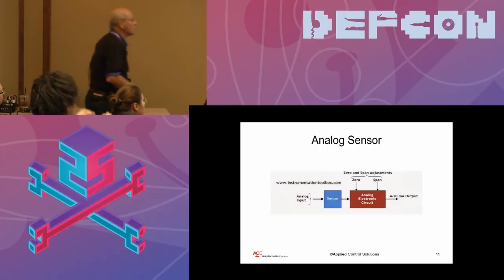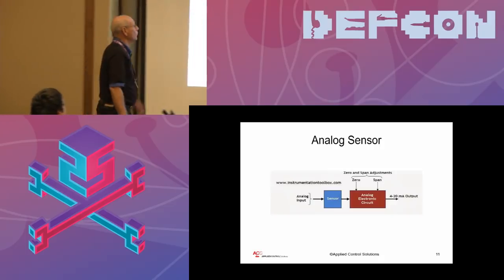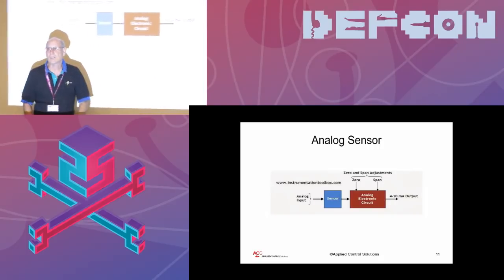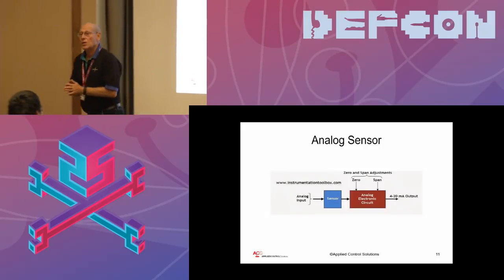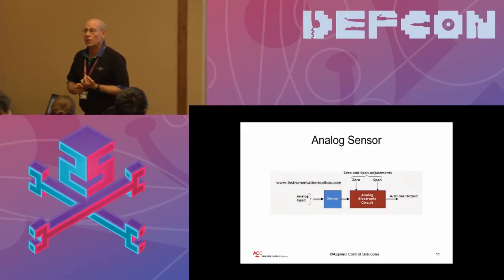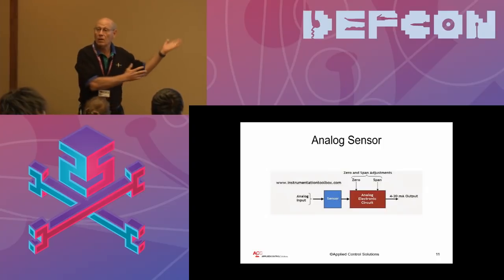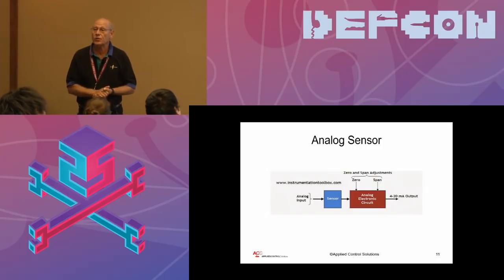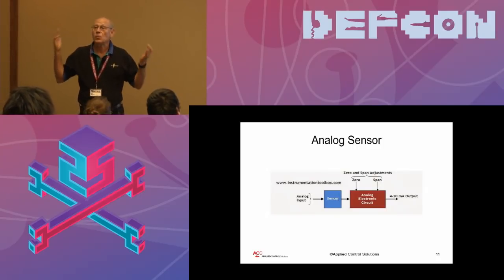This is just the sensor. And again, here's the point. What you're doing is you're coming back in, and if you change things like zero and span, you can prevent a sensor from ever reaching a set point, or make it reach a set point long before it should. And you will never know that from network monitoring.